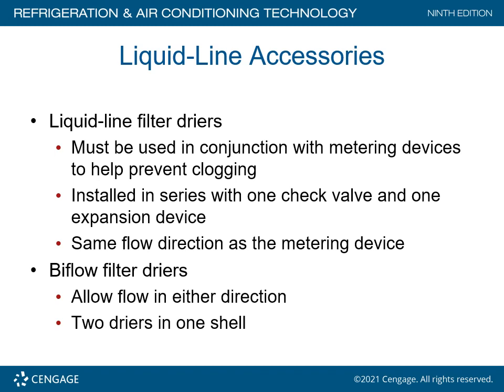Has to be. If you put in a single direction filter dryer instead of a bi-flow design, the molecular sieve inside the filter dryer will be allowed to deteriorate and start plugging up things inside the system. This is a very serious situation. So please, when you install a heat pump, make sure you have a filter dryer which is designed to flow in either direction.